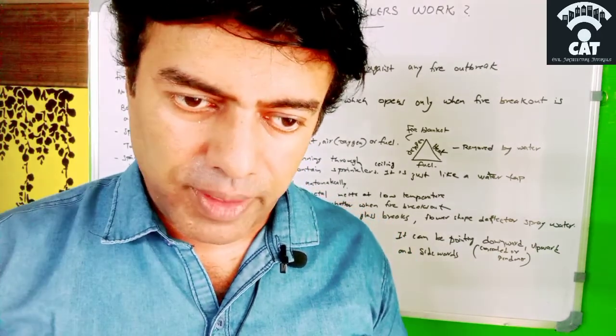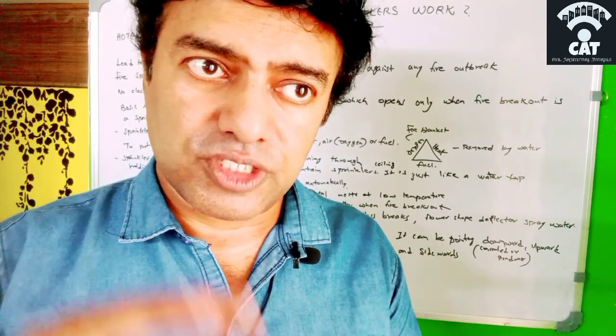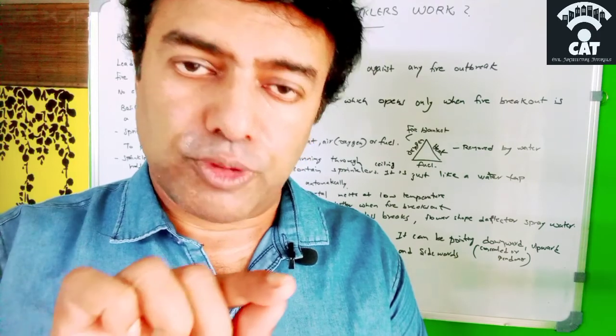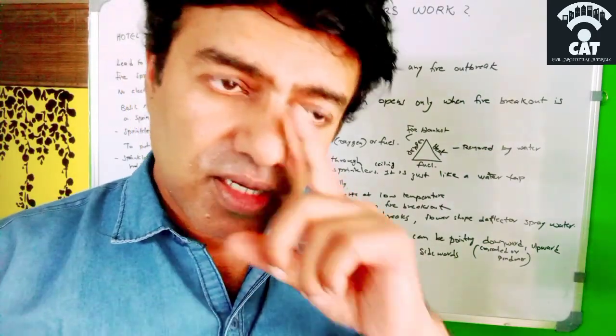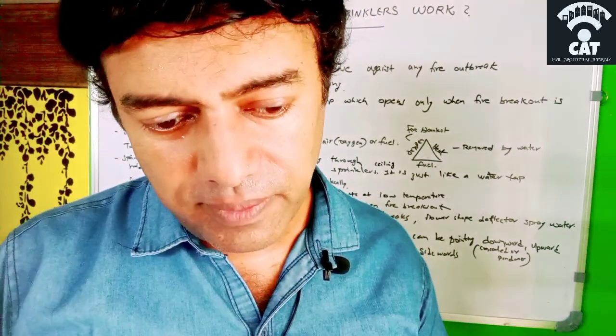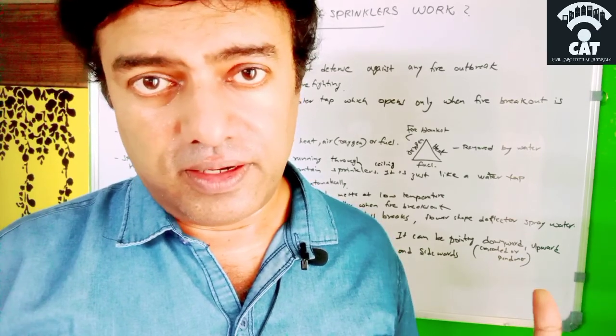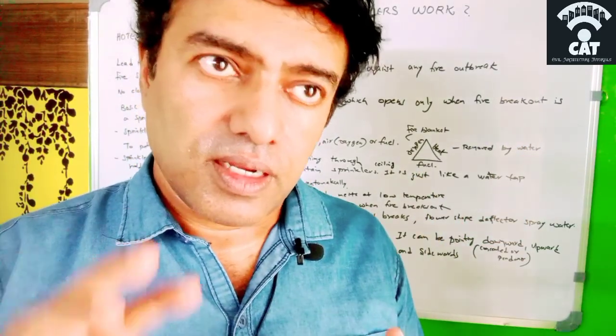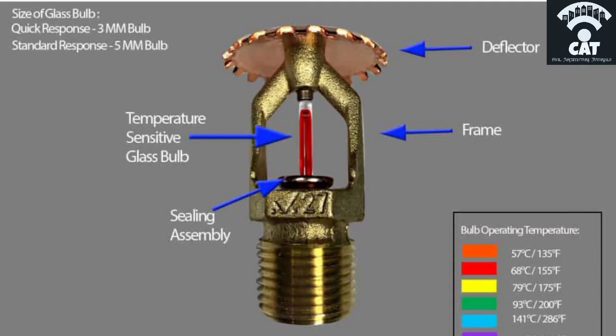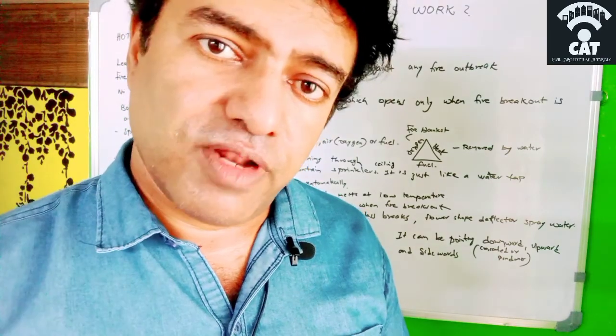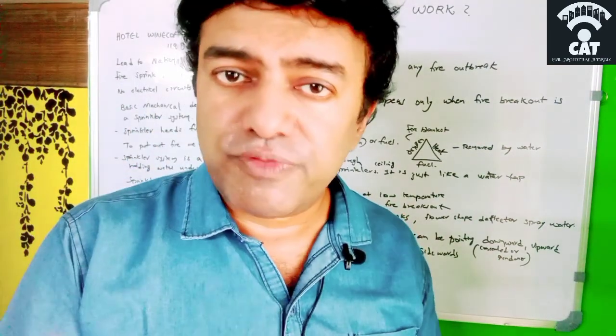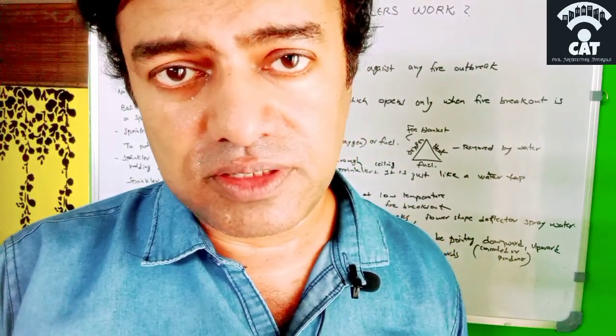When a fire breaks out in a particular room, the sprinkler system is designed such that it detects heat up to a certain degree. For example, if it is 57 degrees Celsius, then when the fire breaks out, it produces a lot of hot air. This hot air will rise up first and come into contact with the sensors of the sprinkler. If it reaches 57 degrees, the plug of the sprinkler, which is made up of either a metal alloy called wood metal or a glass tube filled with a glycerin-based liquid, will burst when it reaches 57 degrees Celsius. It could be 50 degrees. It depends on the temperature at which it has been designed to burst.